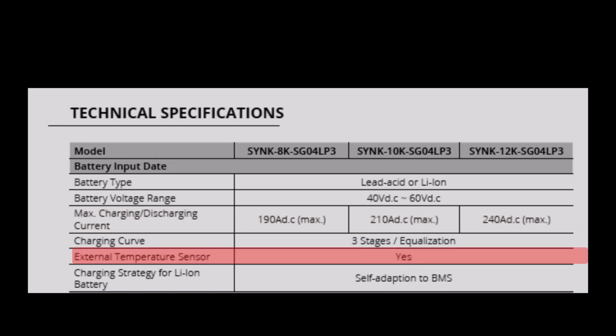The three-stage charging curve is common to most modern batteries, and it consists of three stages. The first stage is bulk charging, where there is a constant current and the charger delivers a maximum allowable current to get the battery up to about 90%. The next phase is the absorption phase, where there is a constant high voltage and the current gradually decreases until the battery is at about 98%.